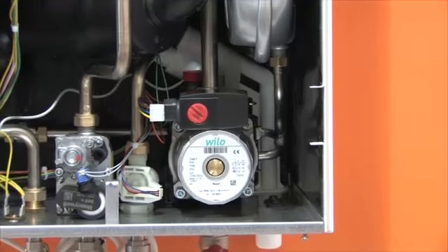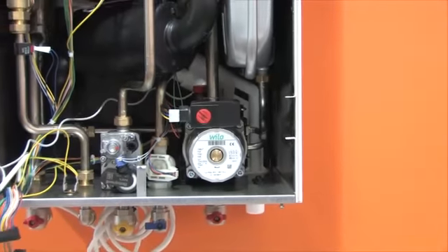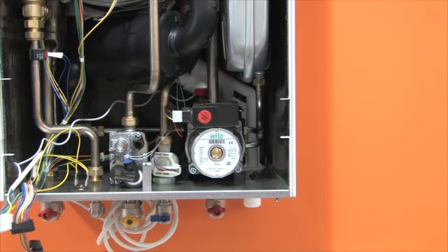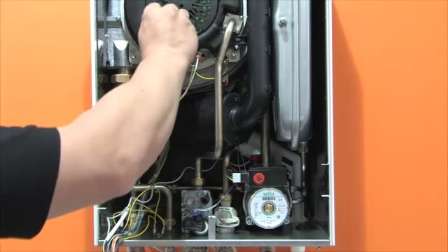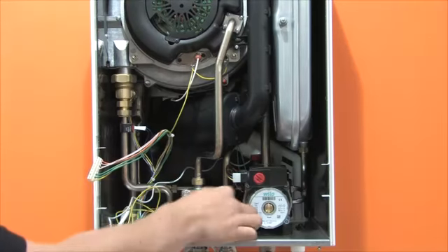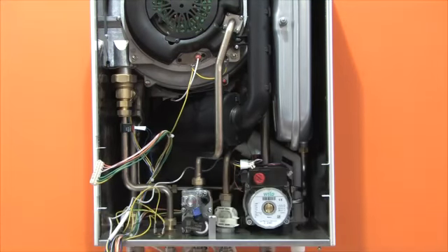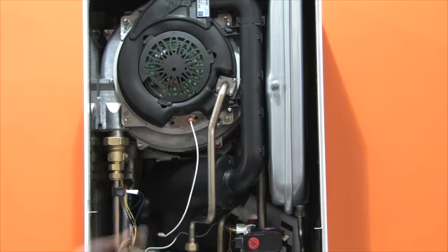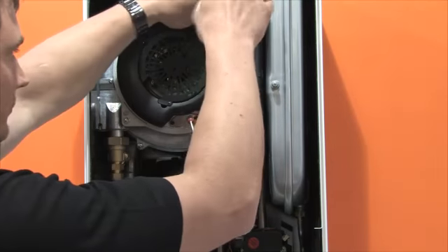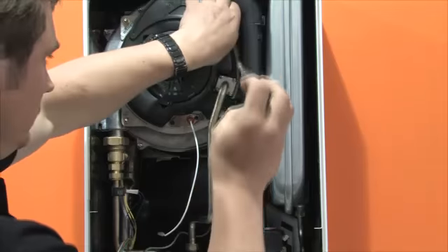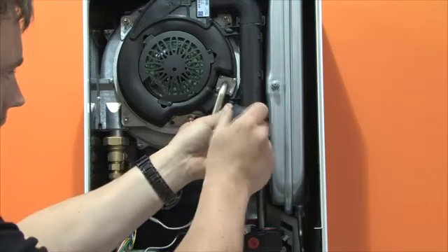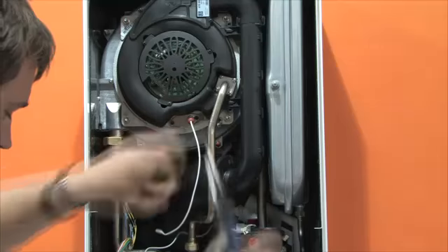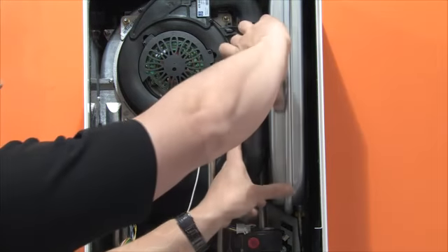It is now clear to see what's behind the superb reliability record and high performance of the Modena. Only 4 moving parts means there is less to go wrong, and diagnosis of any problem is easily identified. The fan is simple to disconnect, and the gas valve, flow switch and pump are all connected with just 1 push-on and off plug. As well as being the lightest, smallest boiler in its class, it is also the quietest. The air silencer is removed by taking out 2 retaining screws from the top, releasing 2 clips, and pulling down and away.